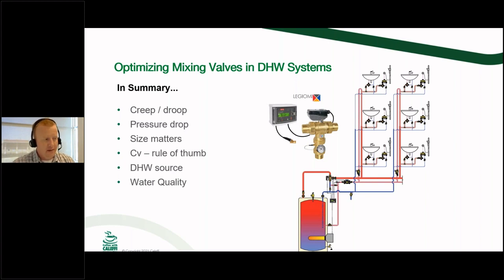Your thermal balancing valves are a dynamic balancing valve. They are not going to be a fixed flow type balancing valve like what you're going to find with your manual balancing valves. So a thermal balancing valve is potentially going to help, because as the temperature starts to come up, it's going to start to close off that balancing valve more and more. But thermal balancing valves never close off 100%, so you're still going to get flow through there. So it's one of those maybe scenarios. There's no 100% proof that it's going to completely eliminate the scenario. It can't hurt, but in the same breath, I can't guarantee it's going to fix it 100%.